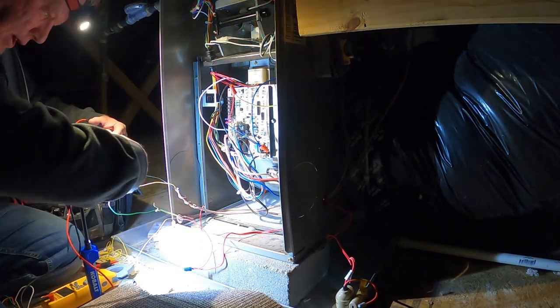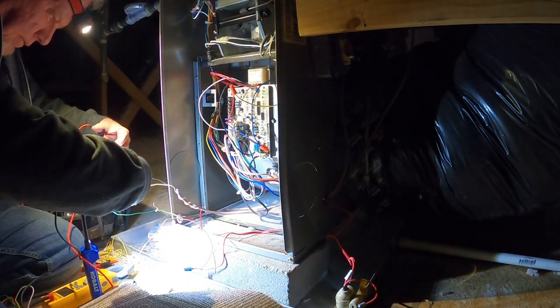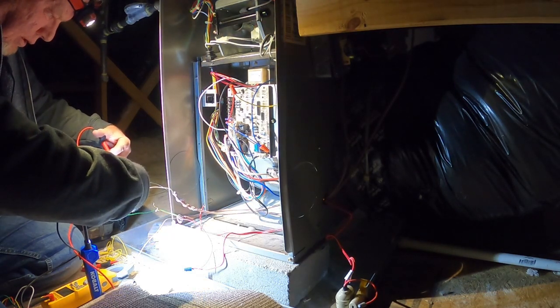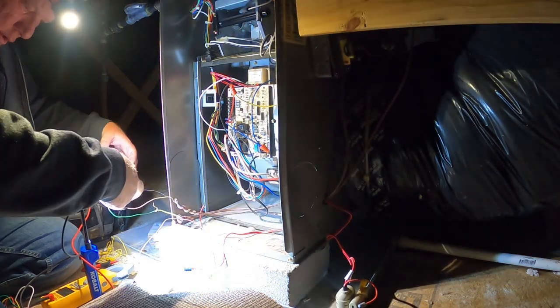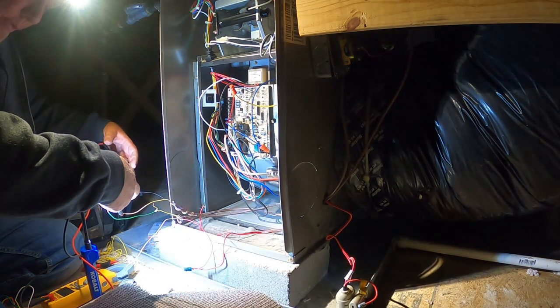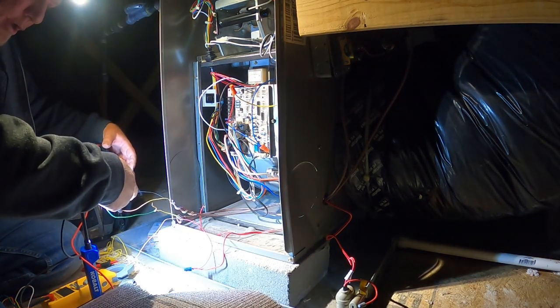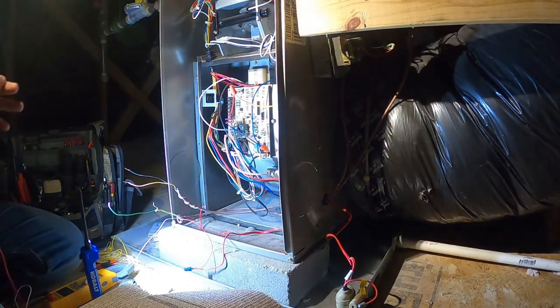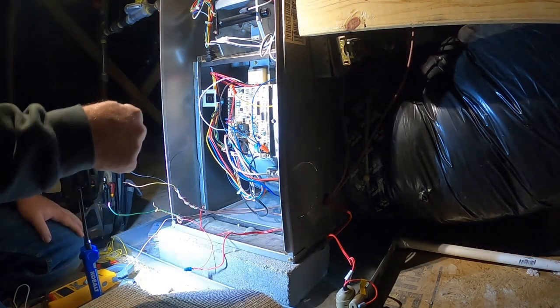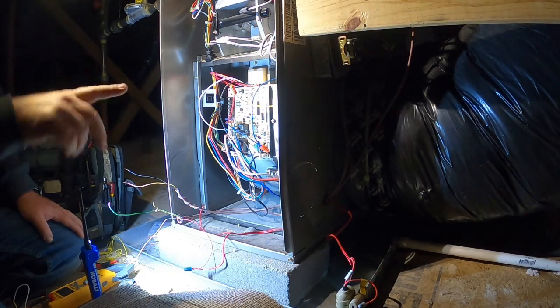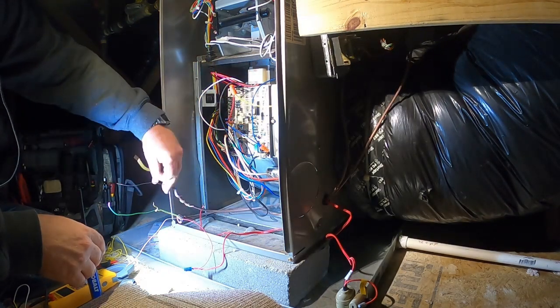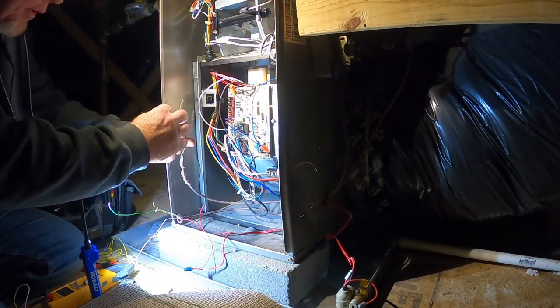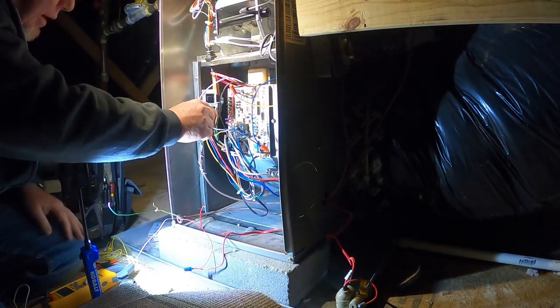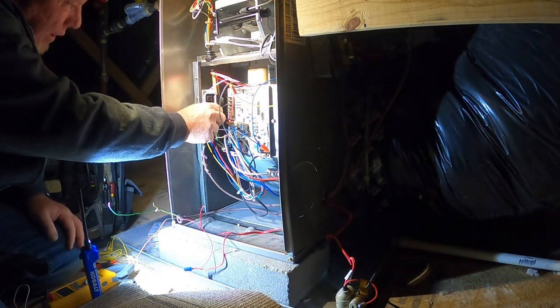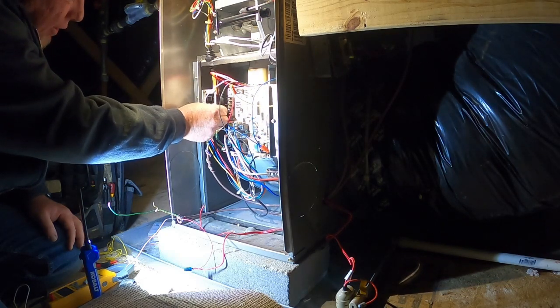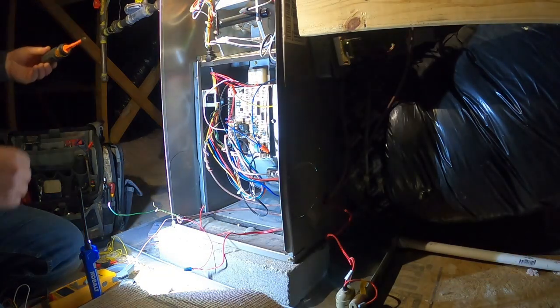And the contactor was bad, but okay, so I had 13.5 out there. I've got 14.3 up here, so should be good. It is going through a load management box before it goes to the outdoor unit. Some people have those on their houses. I think they suck. Anyway, you turn your air conditioner off when you need it to be working most, which never made sense.